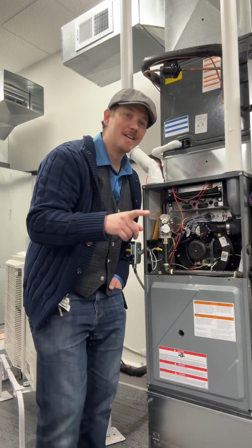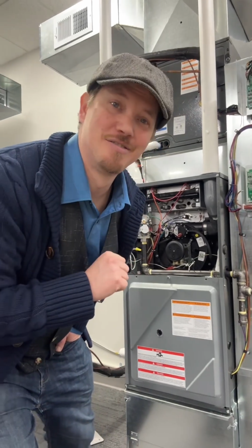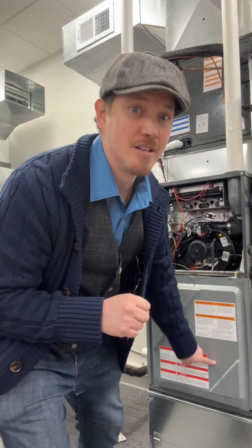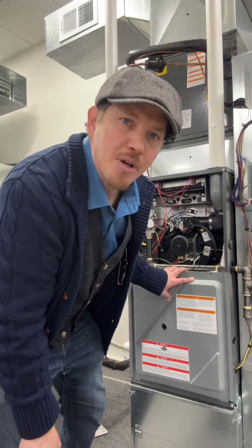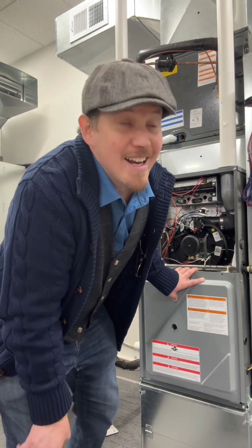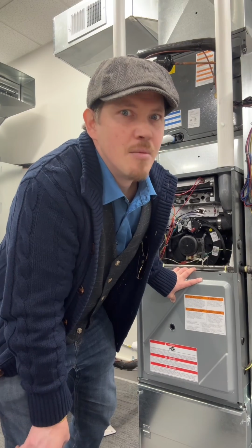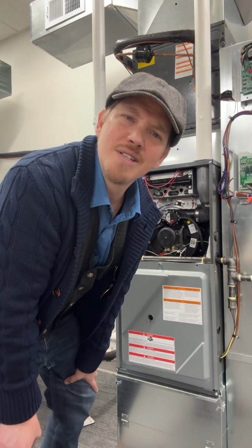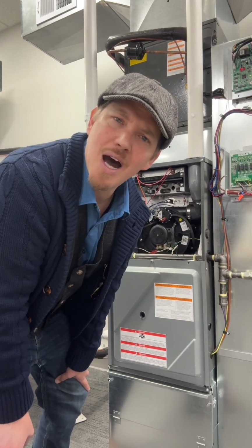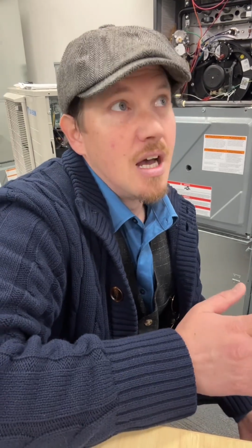What piece of equipment cares? I can tell you what piece of equipment cares. That blower motor cares. This blower is rated for 0.5 because it can handle up to 0.8, but we don't like it. And what does that mean for your customer if your static's too high? If your static's too high on your system, it can cause oil return issues, kill your compressor. It's gonna cause noise issues, kill your income, because if your customer's not happy, you're going out there a lot. I don't want you to go out there a lot.